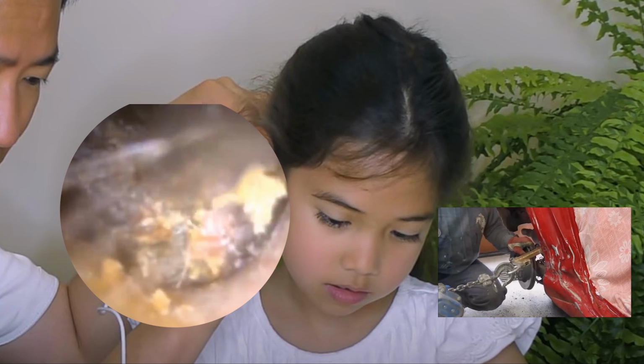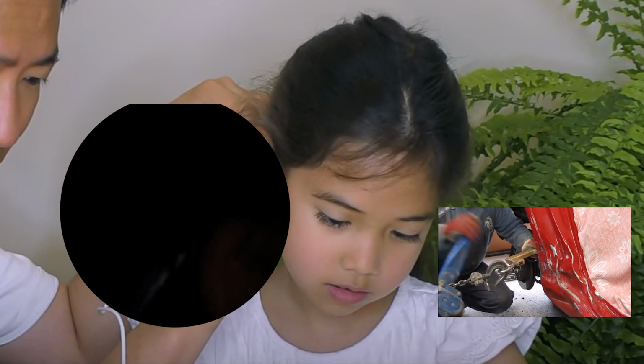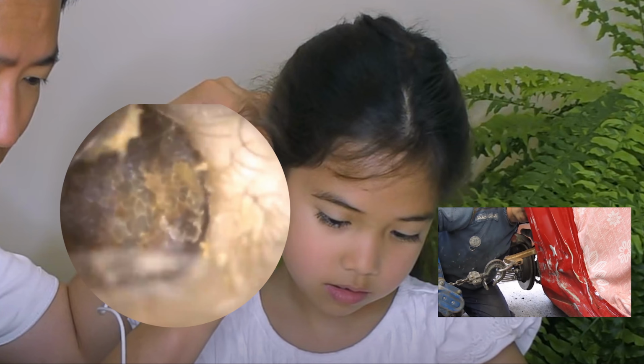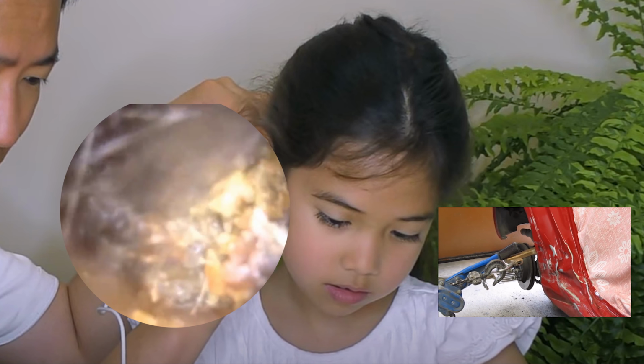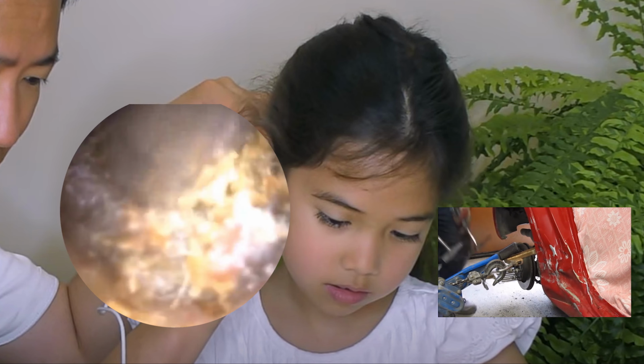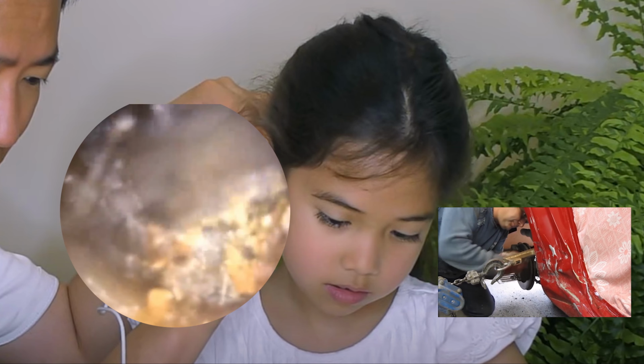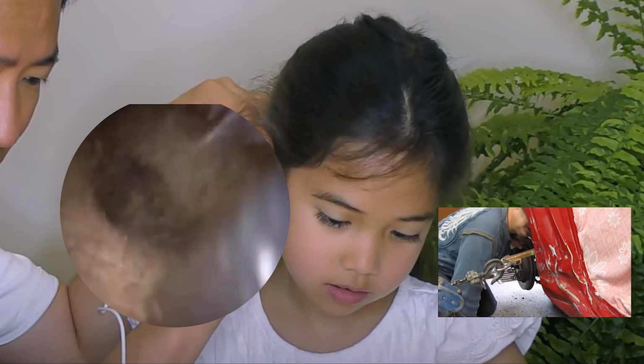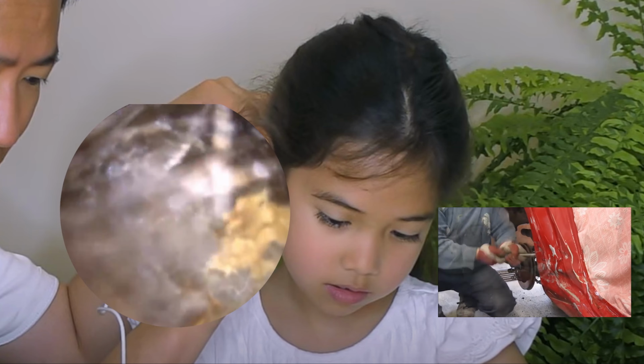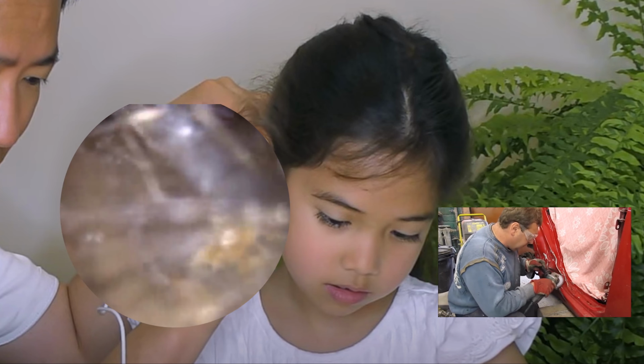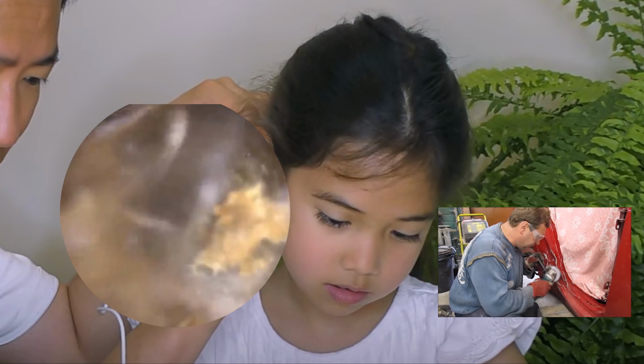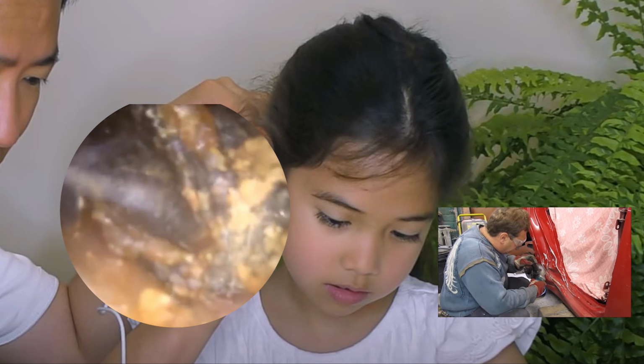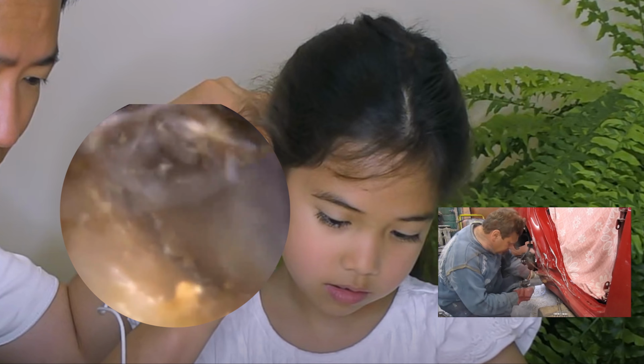But when developing the wax scope, I was trying to incorporate some of the key benefits of an endoscope. And I think with an endoscope, it's the view you get with the instrument, it's always in focus, because the instrument's so crucial, being able to see that clearly, because you are, of course, inside someone's ear, and you don't want to be causing trauma by bumping into the canal walls, or worse still, the tympanic membrane. And we've got a lateral slit. It's also a Tumarkin style speculum, so there's a slit at the roof of the speculum, which you use to insert the instrument in. So it's coming from a higher angle of incidence. And that's what typically you do with an endoscope.